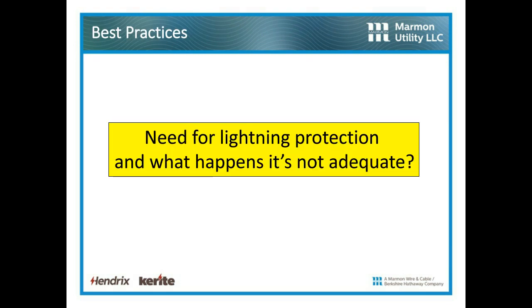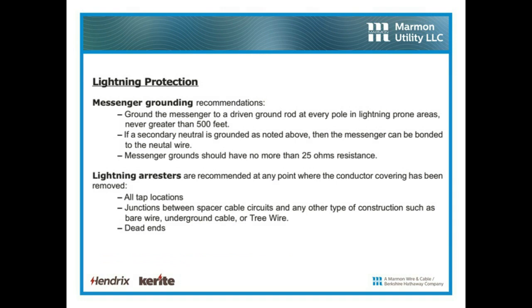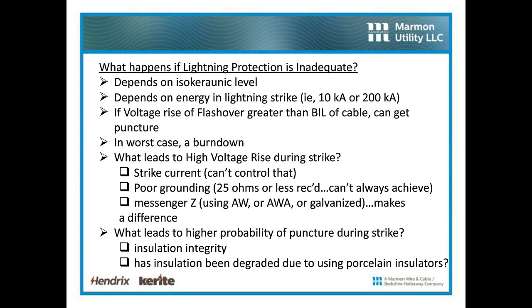What happens if lightning protection is not adequate? We have lightning protection recommendations in the catalog. Essentially, I'm going to use a grounded messenger every 500 feet or less at all tap locations, junctions between spacer cable and bare wire, underground cable or tree wire, and at dead ends. And if lightning protection is inadequate, it depends. You might not need it. It depends on how big the strike is. In the worst case, you can get a burn down.